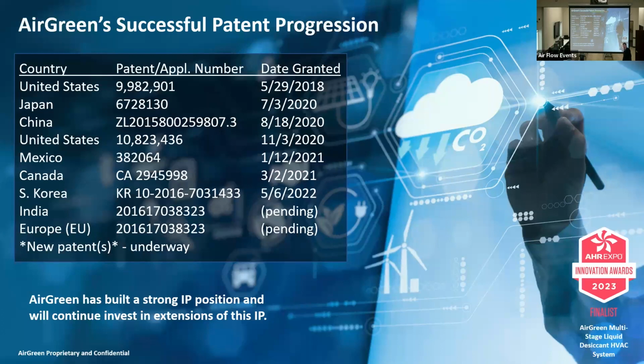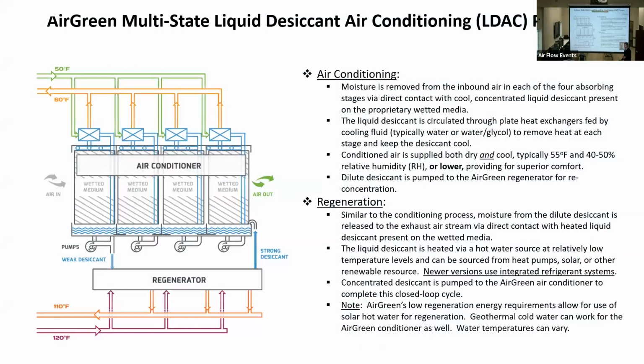There are obviously liquid desiccant systems out there. Kathabar has one, a single stage packed tower with media for their regeneration. Ours is a media-based system. We have basically a fabric that is corrugated. It's like a Munters style media that gets used in evaporative cooling applications. Same sort of setup. It absorbs 4 to 5% of its weight in liquid desiccant. So we present to the airstream a cool surface that is wetted out with a concentrated desiccant solution, which will strip the air and cool it at the same time.